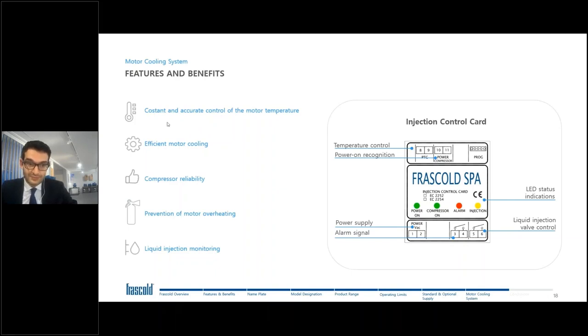So, resuming a little bit all the benefits: there is a constant and accurate control of the motor temperature. The motor cooling is efficient because it's done only if needed, otherwise it's not done. In this way, the reliability of the motor itself, and so of the total compressor, is absolutely increased, and there is the prevention of motor overheating. And the liquid injection is not constant, is not done as soon as you switch on the compressor, but it's monitored. So it's only done if it's needed.